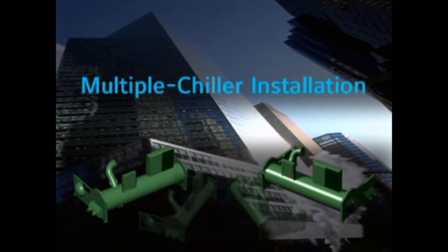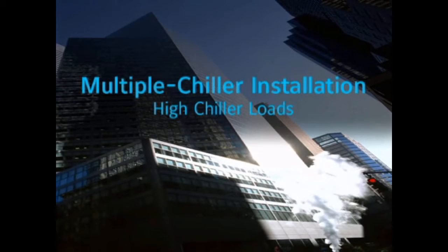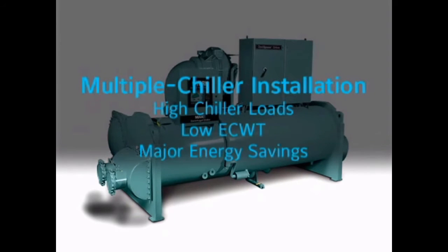OptiSpeed Drives will save in both single chiller installations and multiple chiller installations. In multiple chiller installations, cycling chillers off as the building load falls will result in higher loads on the remaining chillers. This would seem to reduce the opportunity for OptiSpeed Drives to save energy. But keep in mind that even though chiller loads remain high, the entering condenser water temperature has most likely fallen. And reductions in entering condenser water temperature offer a far greater potential to enhance chiller efficiency than load reductions do. So OptiSpeed Drives deliver major energy savings in multiple chiller plants too.